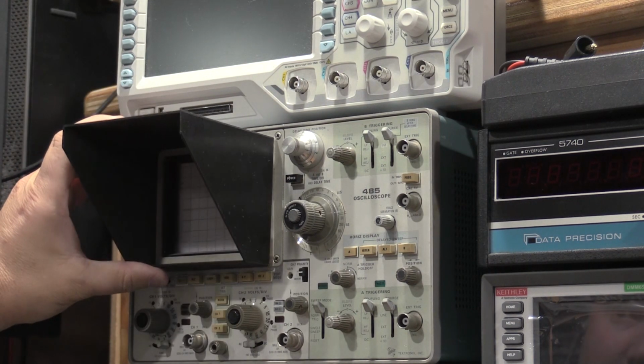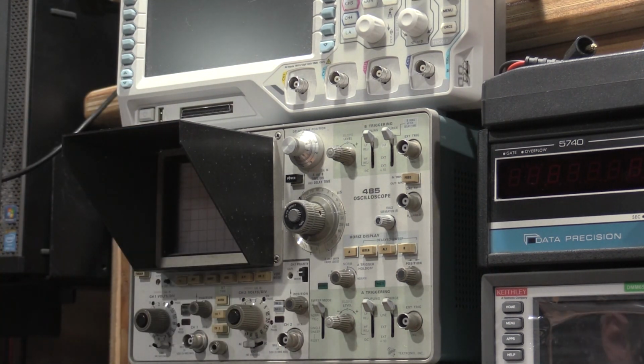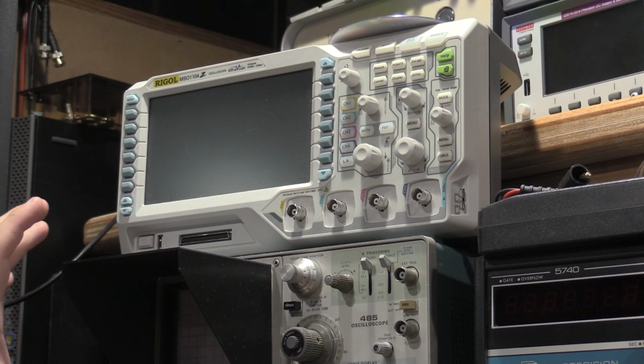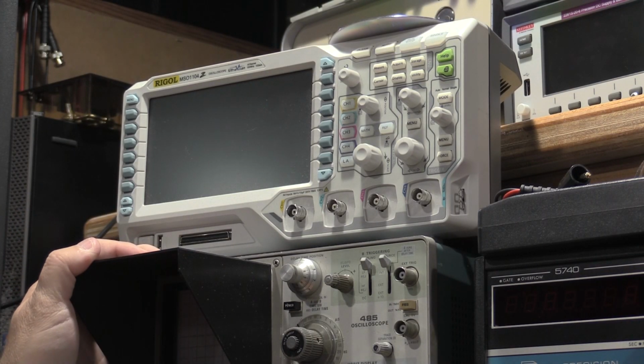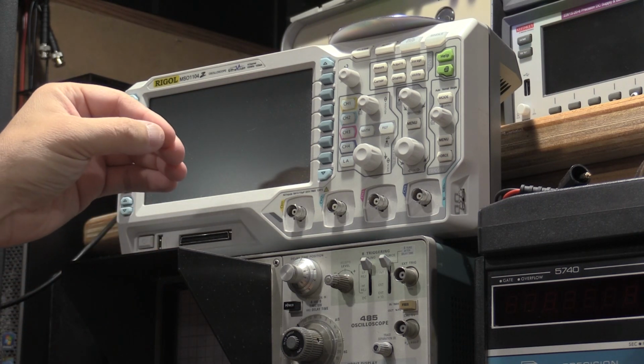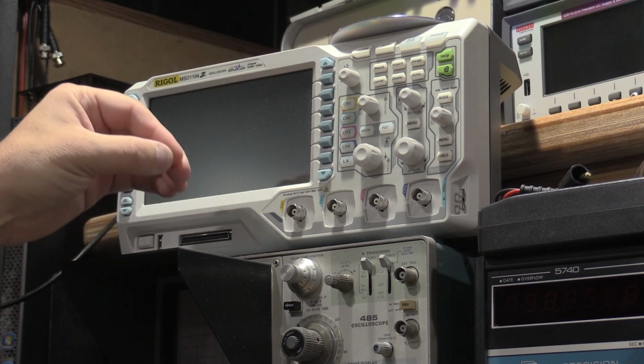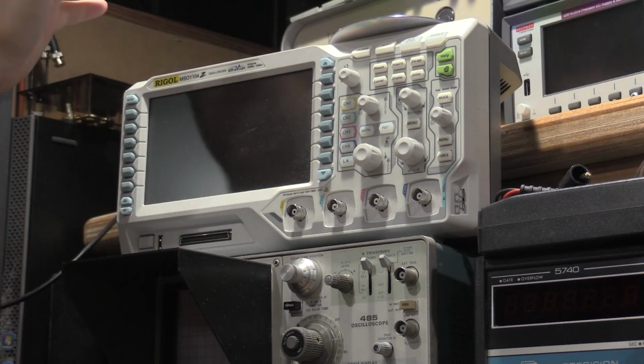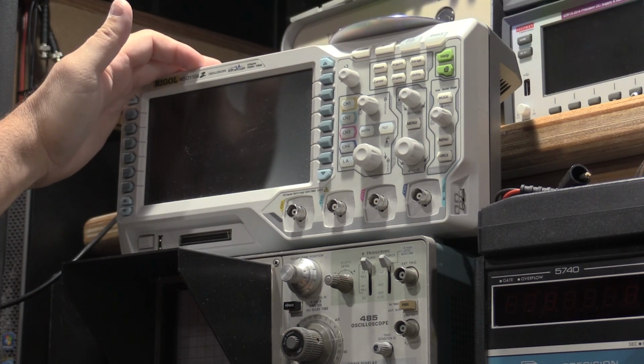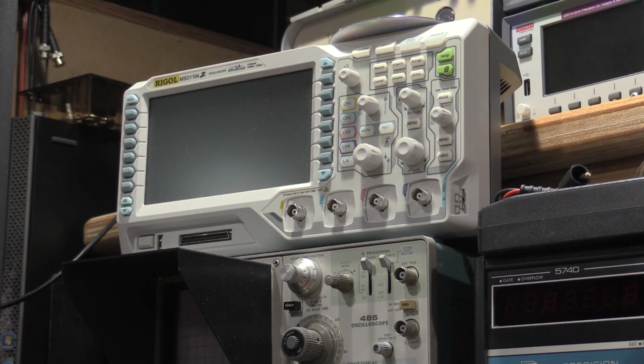However, I've done a lot of scopes on this channel, and a lot of stuff from the secondary market. Every single scope I have purchased secondary market that has been inexpensive has needed alignment and calibration. It has not been ready to go. That is not to say an analog scope cannot be done from the secondary market. However, if you're going to get a scope that's calibrated, it's going to cost about as much as this scope right here, or more, depending on the speed.